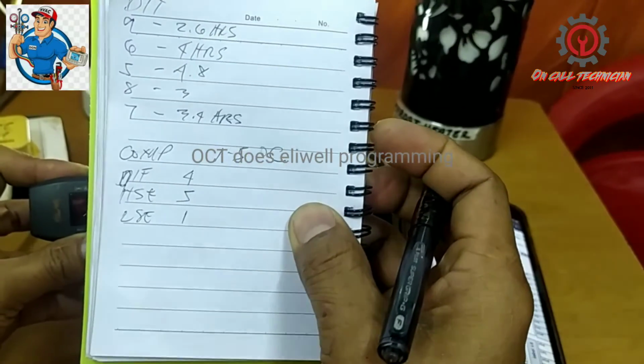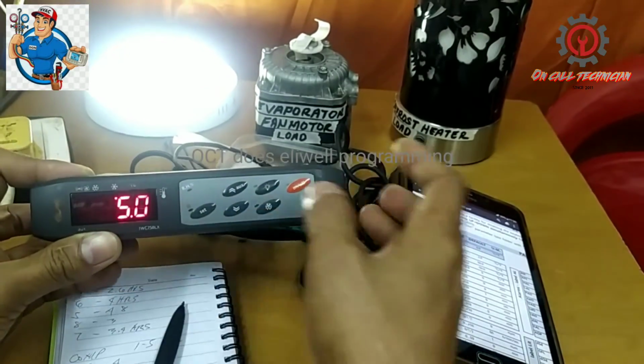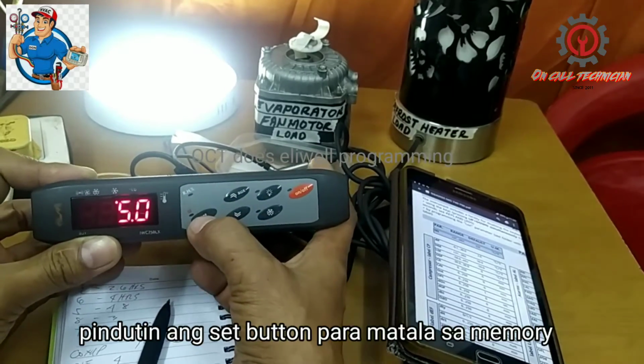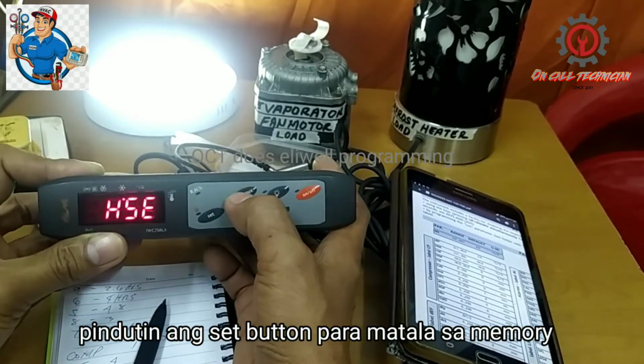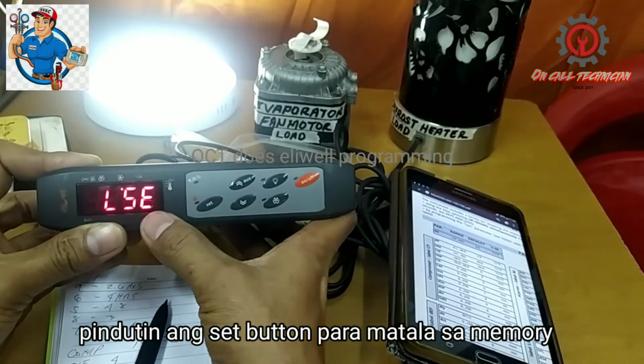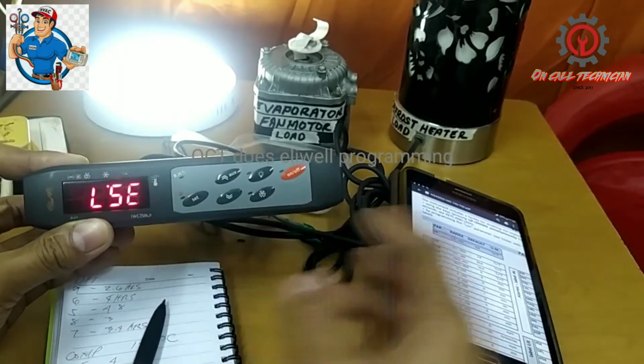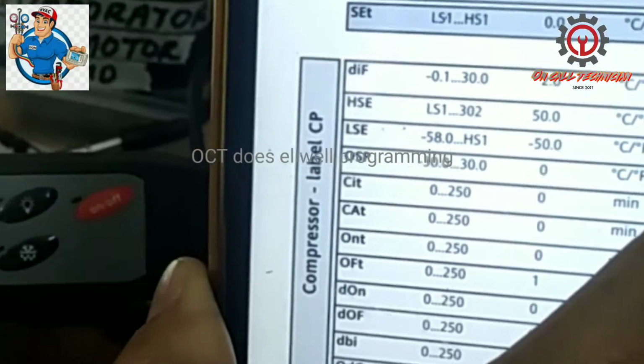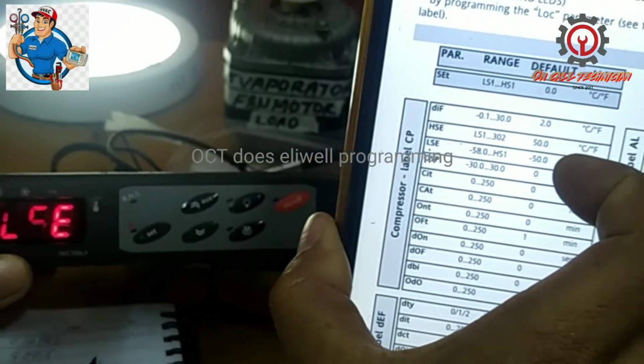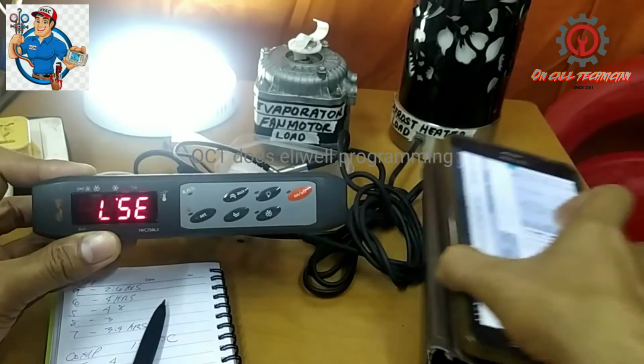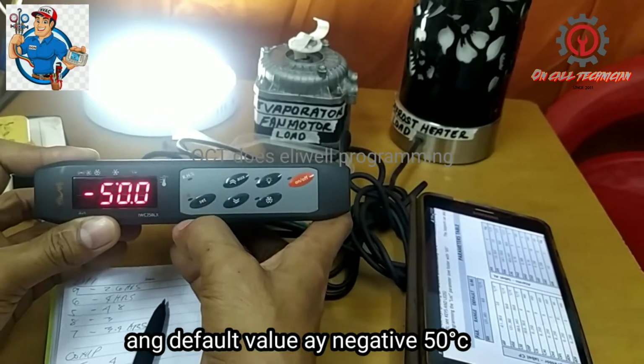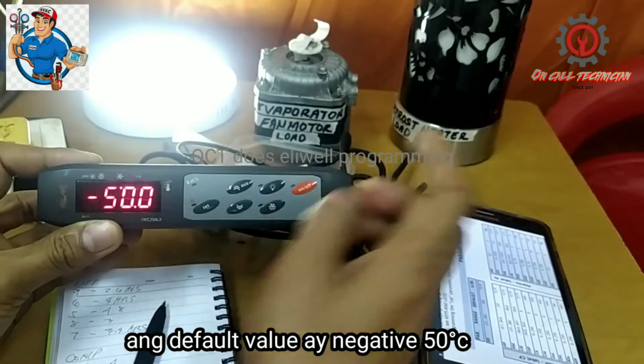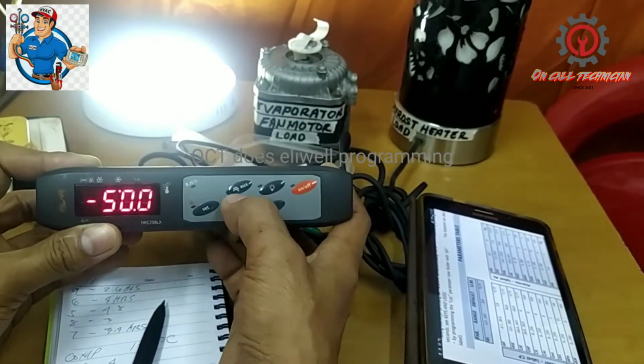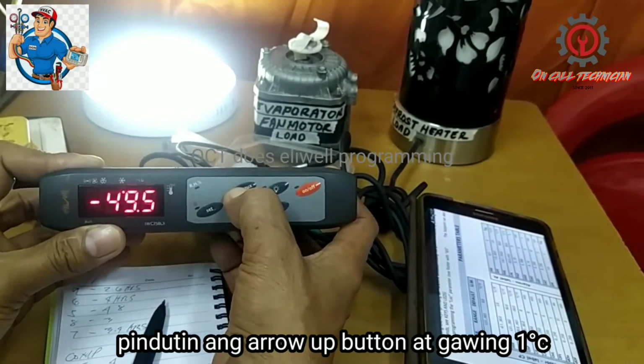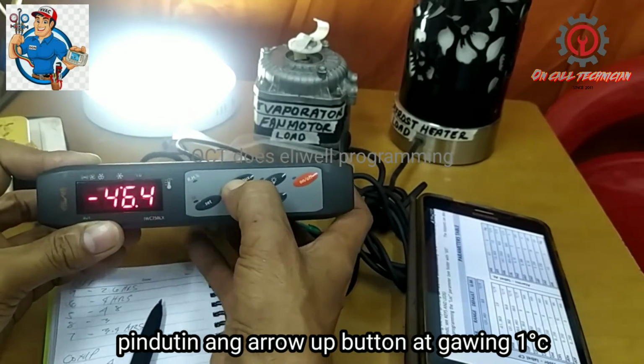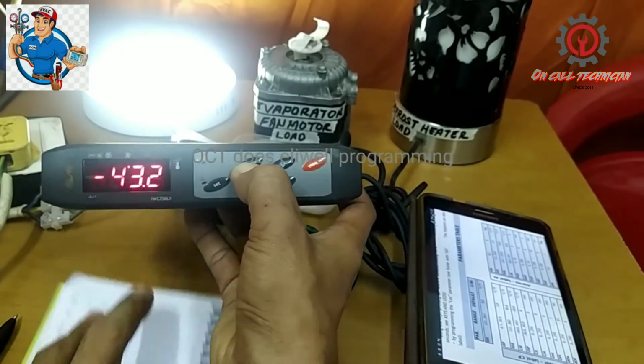Okay, and my LSE is positive 1. So I'm going to press the set button to memorize, and we're going to change the LSE, and what is stored here is negative 50. So we're going to change that to positive 1. Set to show the value, and the value is negative 50. I'm going to change that to positive 1.